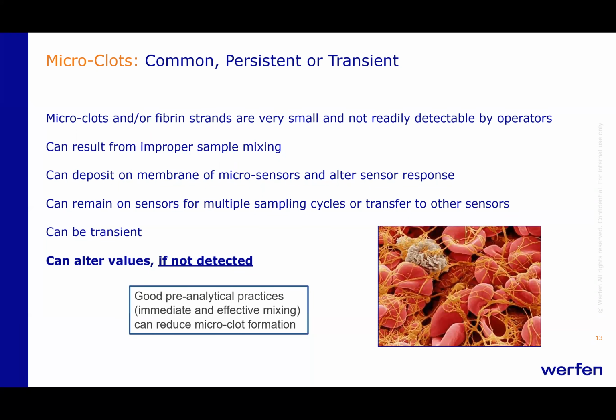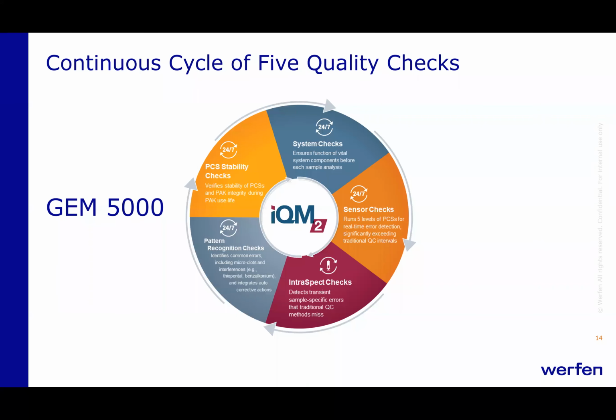So immediate and effective mixing can reduce microclot formation. The GEM 5000 uses a continuous cycle, 24/7, 24 hours a day, 7 days a week, of 5 quality checks to help ensure accurate results. And I'll show you some studies from what we were able to determine from GEM 5000s with IQM2. So system checks ensure function of all the vital systems, such as the sample pumps and the process control pumps, the aspiration method and probe, and for each sample analysis to assure that the sample was aspirated correctly.